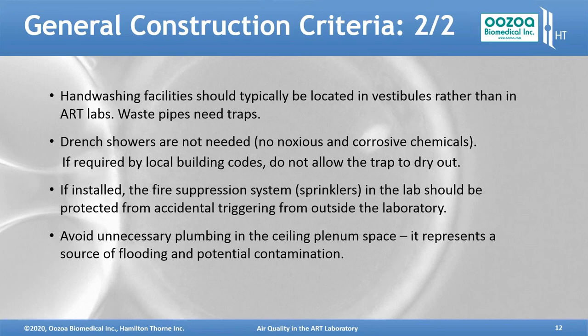If installed inside the lab, the fire suppression system, sprinklers, should be protected from accidental triggering from outside the lab. You don't want a paper fire in a nearby office area to set off the sprinklers inside the lab and destroy $500,000 worth of equipment, for example. You need to avoid unnecessary plumbing in the ceiling plenum space. This is the space above your fixed ceiling, but if the plumbing there leaks, it's a source of flooding and potential contamination of your clean room, and it's complex and expensive to remediate afterwards.